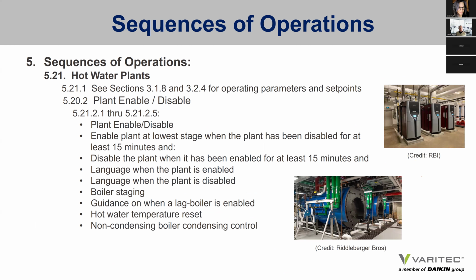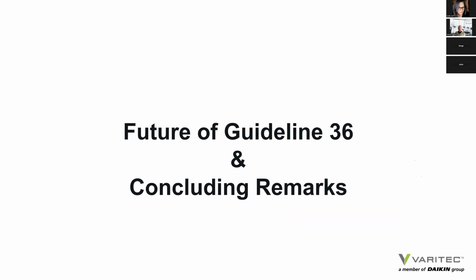It also has now sequences of operation for hot water plants as well. That somewhat mirrors the chiller operation. That is to say, when is a boiler to be enabled, disabled, enable plant at the lowest stage when the plant has been disabled for at least 15 minutes, disable the plant when it has been enabled for at least 15 minutes, etc., etc. All of that language on hot water plants is involved in the guideline that we certainly don't have time to go into today.